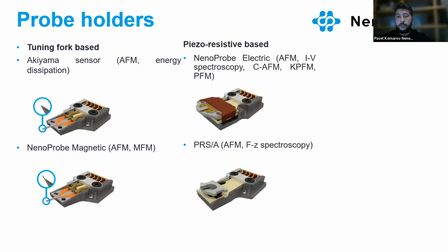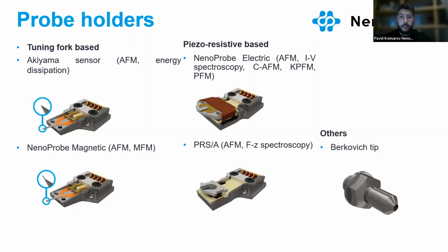And the second group is the piezoresistive-based probes, which are applied to measure electrical properties, such as surface charge by Kelvin probe force microscopy, the piezoelectric effect by the PFM technique, and of course mechanical properties measured by force-to-distance spectroscopy. And as an accessory, we also created an additional nano-indentation module, thanks to our friends from the Alemnis company. So we can install an additional nano-indenter over the LiteScope AFM, all inside the SEM chamber, so that you can do a complete set of measurements together with the SEM characterization and in situ. In the case of nano-indentation, we are using the Berkovich type.